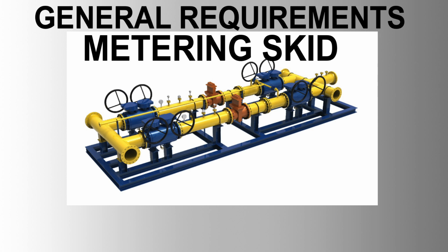Specific installation requirements. Meters should be installed in straight runs of pipe to ensure accurate measurement, with minimum upstream and downstream straight lengths as per manufacturer recommendations. Strainers should be installed upstream to prevent debris from damaging the meter. Pressure and temperature transmitters should be installed to correct measured values for accurate volume flow calculations.